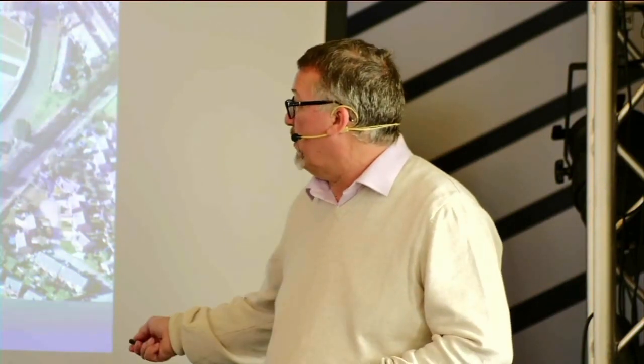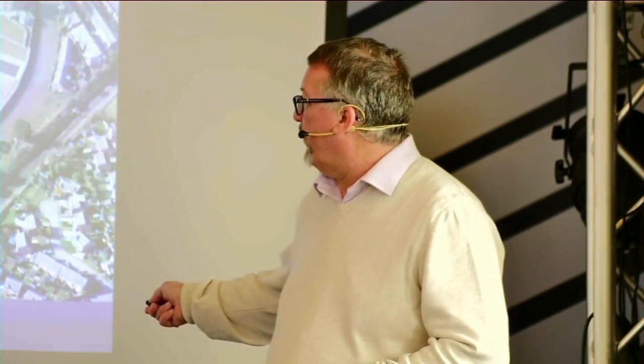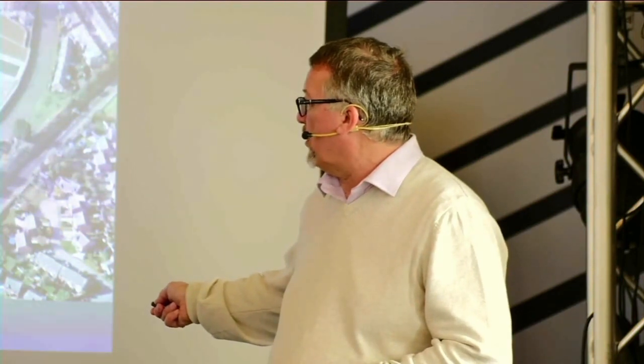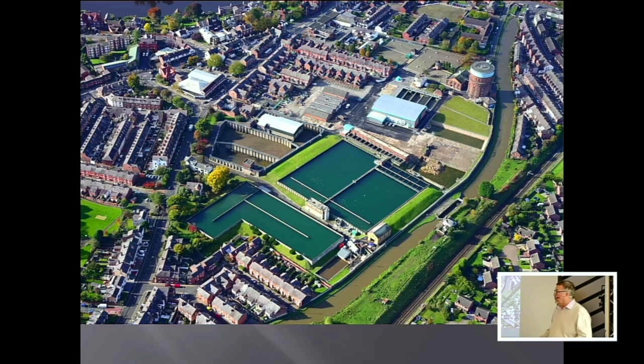And of course, most of these are underground, they go deep into the ground as well. But we don't cause damage. We had an overflow in the new one due to control system failure that actually collapsed part of the canal wall at one point onto the towpath. So again, we had to put remedial measures in and upgrade the system to stop that happening again.